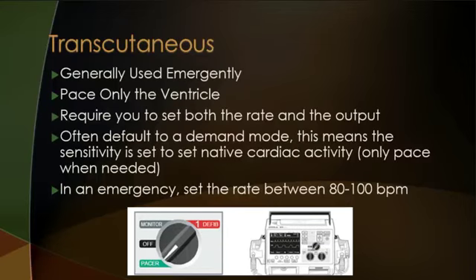Transcutaneous pacing, like we said, is generally emergent. It only paces the ventricle. It requires you to set both the rate and the output, and until you set the output, it won't do anything, because our defibrillators default to an output of 0. It often defaults to demand mode, so this means the sensitivity is set to native cardiac activity and it will only pace when it's needed. In an emergency, set the rate between 80 and 100.